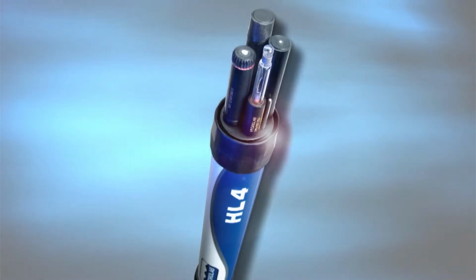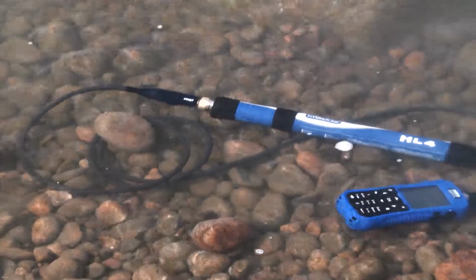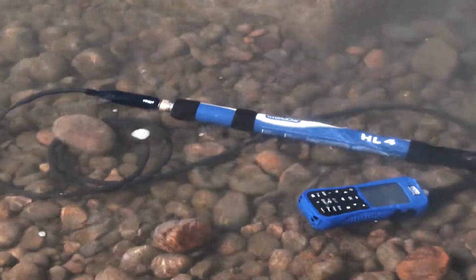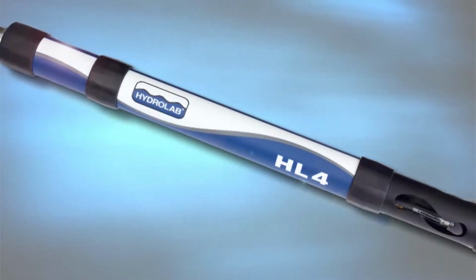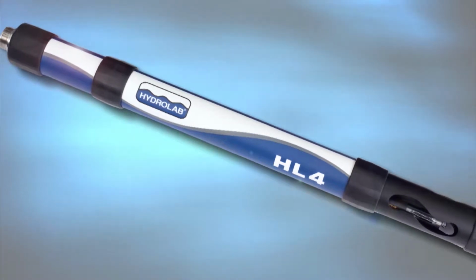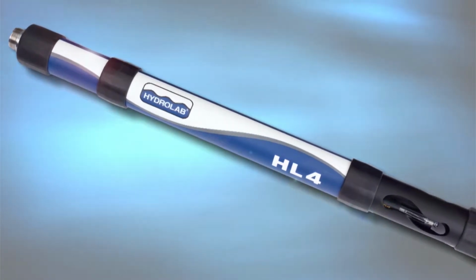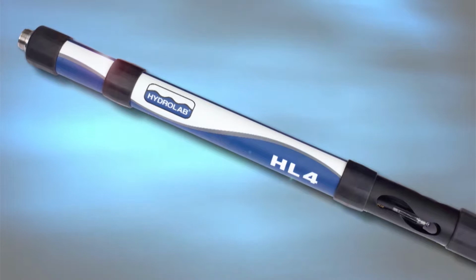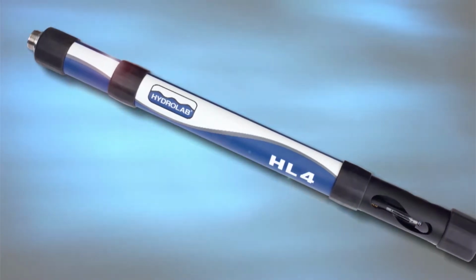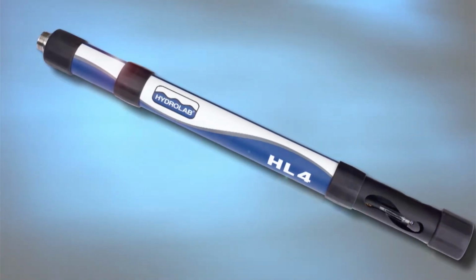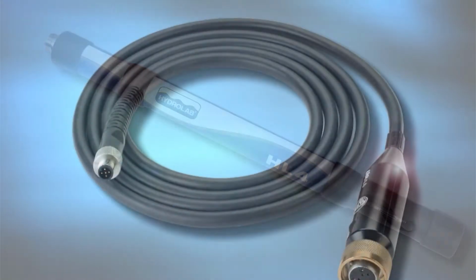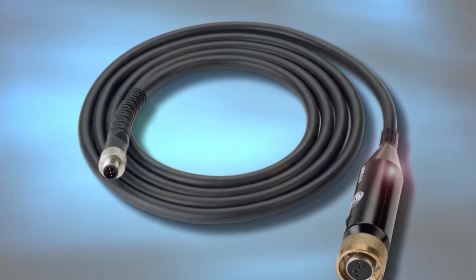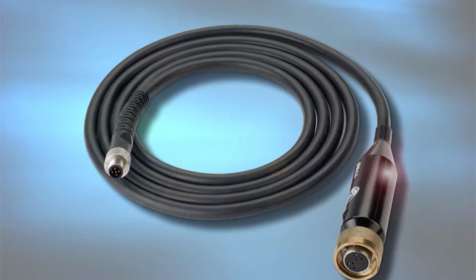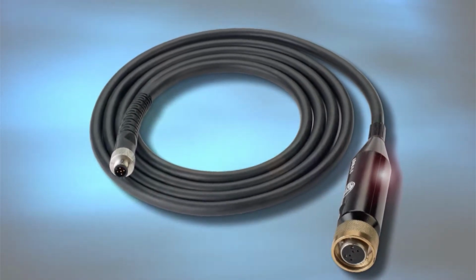The HydroLab HL4 was designed to withstand typical field conditions. Its rugged housing is sealed with tried and true dual O-ring seals and is rated to 200 meters depth. The stainless steel connector is specially treated for extra corrosion resistance, and its pins are recessed to guard them from damage. And field cables are covered with abrasion-resistant coating and strengthened with Kevlar to withstand repeated deployments.